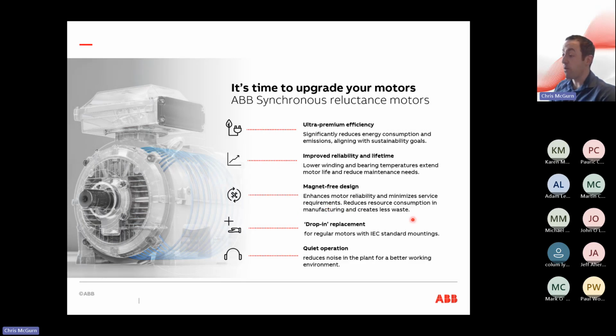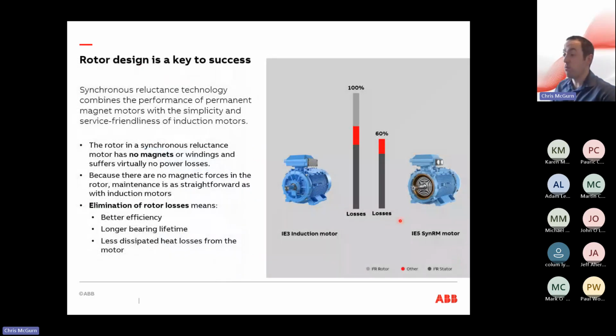These are drop-in replacements for regular motors, so they follow the same IEC standards, the same IEC frame sizes. They can easily switch out with an IE4, an IE3, or an IE2 that may currently be in there. So it's just a plug-and-play sort of replacement. And because of the way they're designed, again, the efficiency, they're quieter. They run a lot quieter than a typical motor, and thus improve the working environment. So why are they more efficient than a typical induction motor?